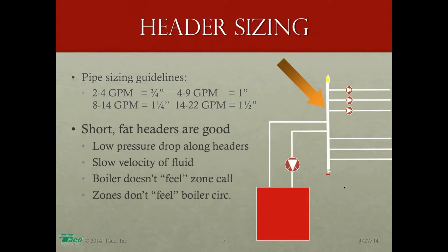Chances are when you set up this system, the required or desired flow rate through the boiler loop is going to be very different and most likely less than the flow rate required through the distribution loop. Right? So in order to keep those two flow rates from interfering with each other, we want serious hydraulic isolation. So oversizing the header, if it says 1 inch, going up to 1.5 inches or even 2 inch can have benefit. Yes, it does add additional cost, but it keeps the two flows separate so they do not interfere with one another. We slow the velocity of the fluid, and at that point the boiler doesn't feel any of the zone calls for heat, and the zones don't feel the boiler circulation.